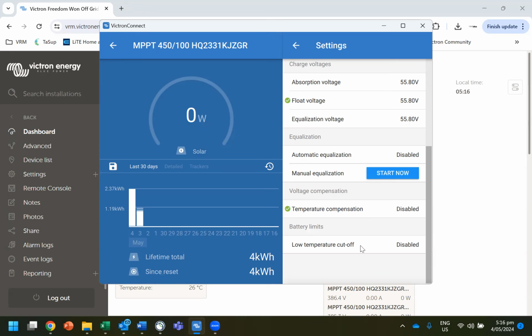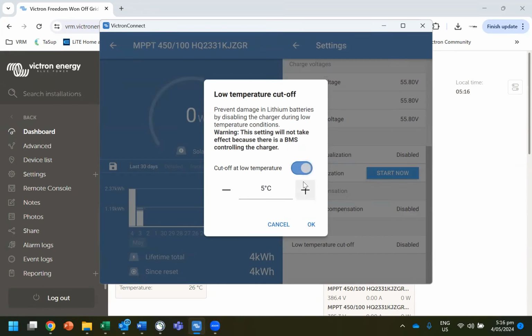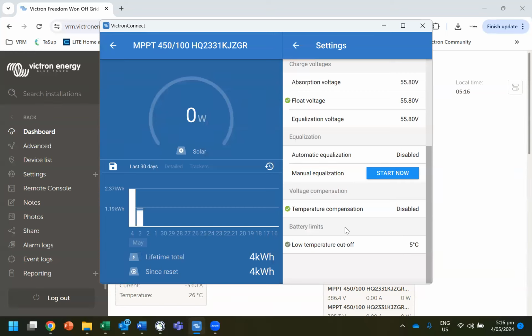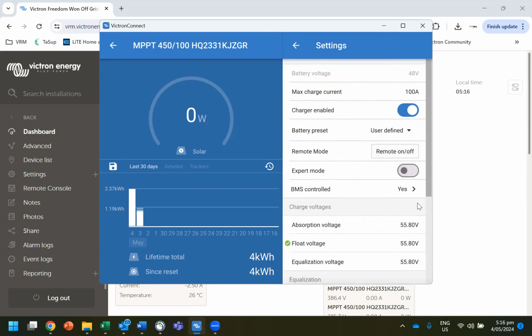Low temperature cutoff. You don't want the battery to charge below zero. The cells should never charge below zero. So we make that 5 degrees just to be safe. If you charge any lithium battery, or any technology that's available now, below 5 degrees Celsius, you risk damaging it. So those are your settings. All done, all looks good.